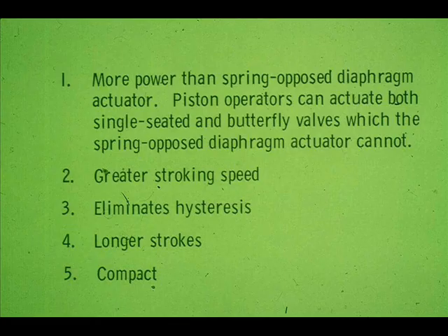As compared to a spring-opposed diaphragm actuator, piston operators offer these advantages. 1. More power than spring-opposed diaphragm actuators. Piston operators can actuate both single-seated and butterfly valves, which the spring-opposed diaphragm actuator cannot. 2. Greater stroking speed. 3. Eliminates hysteresis. 4. Longer strokes. And 5. Compact.